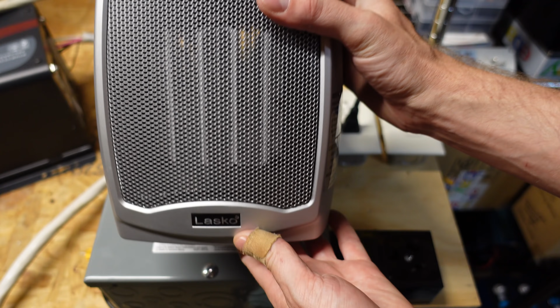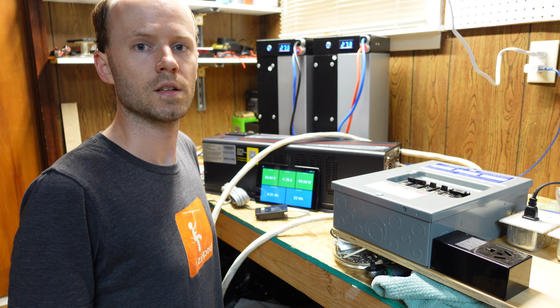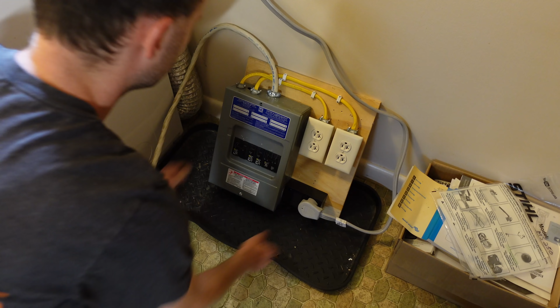No surprise, this inverter has no problem powering that. We're pulling 1.76 kilowatts, 1.81 kilowatts. What I really want to do is see just how much this inverter can take. So I'm going to plug my clothes dryer into this 30 amp outlet and let that run, which should pull around 5,000 to 5,500 watts, nearly maxing this inverter out. Then I'm going to plug in a couple of space heaters because I want to see how much I can overload this inverter.